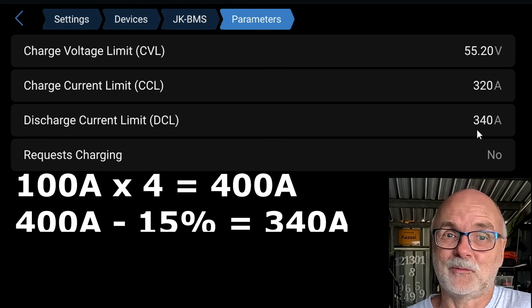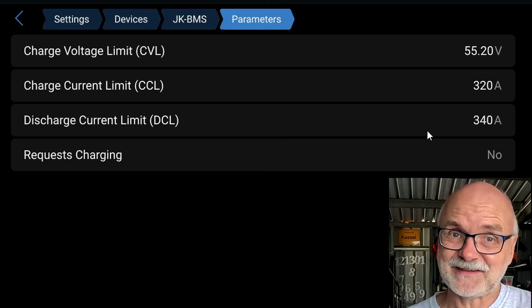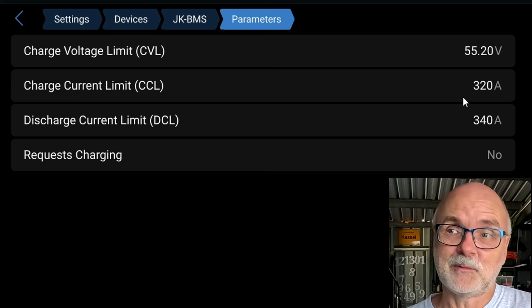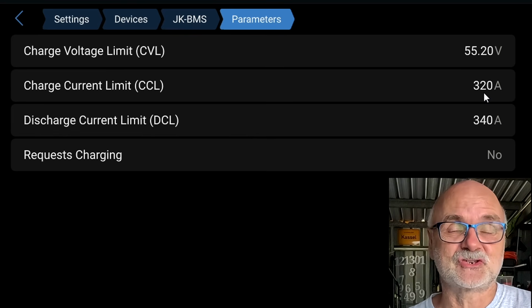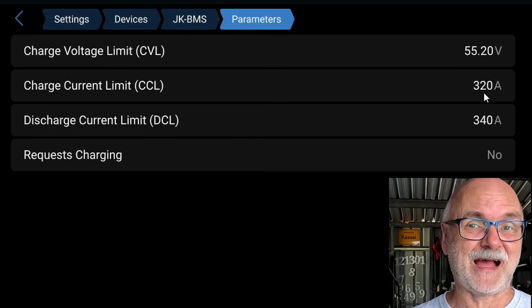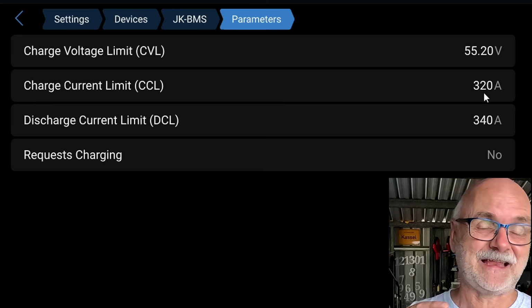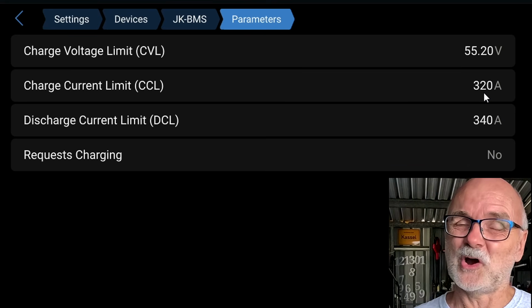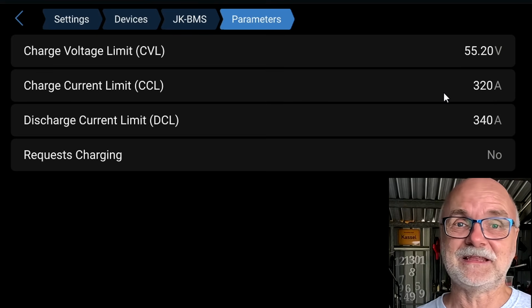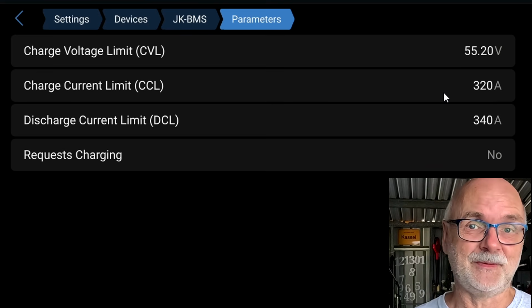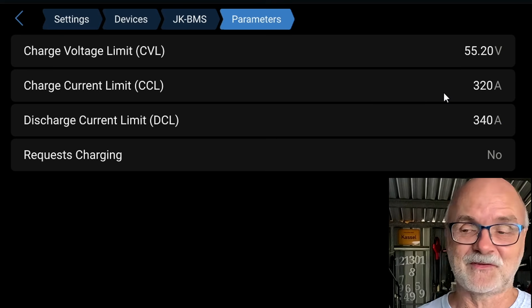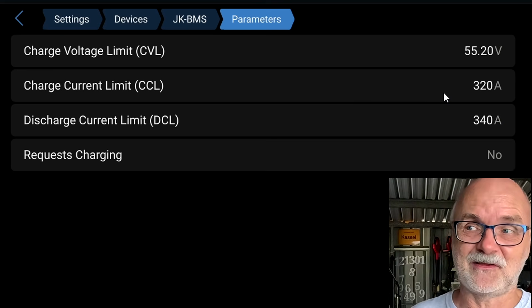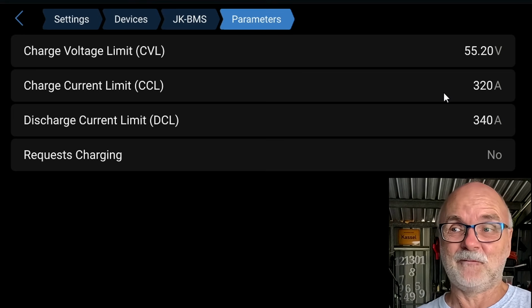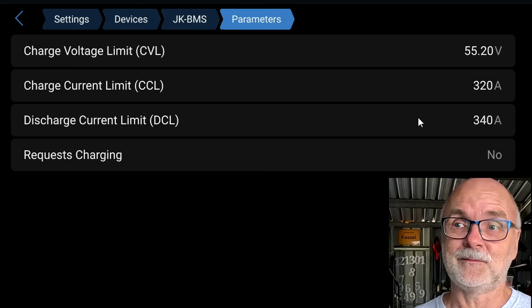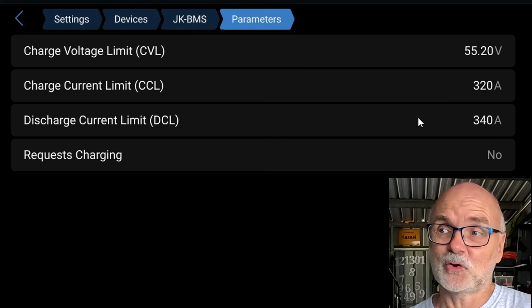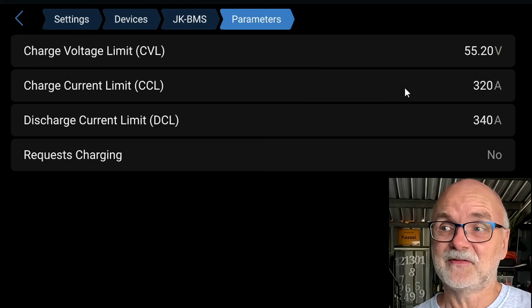But here again, it takes away 15%. The BMS does this to allow for spikes. If we would set 400 amps as a continuous charge current here, and you have larger loads coming on and off, or cloudy weather where the sun comes out and clouds mix, you always go a bit over and under. We would constantly see a disconnect of some of the BMS because you're over these 100 amps, which you have set as a hard limit, as a threshold in your app. So that's why the JK-Inverter BMS takes 20% off of that, or 15% for the DCL, the discharge limit. So that is all good. This would be the maximum charge we're requesting, 320 amps.